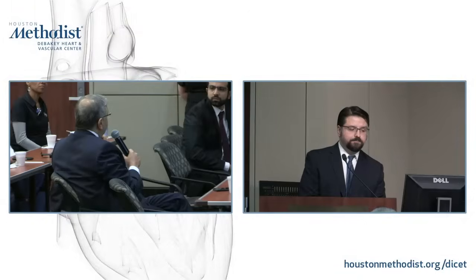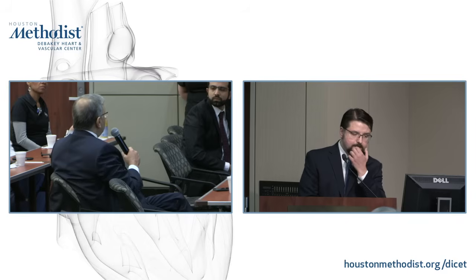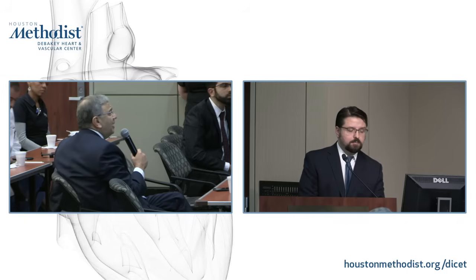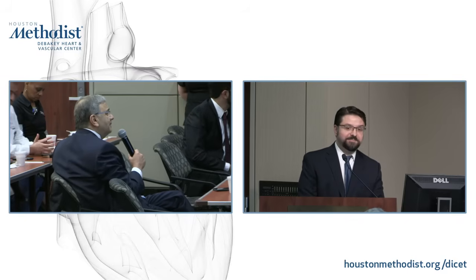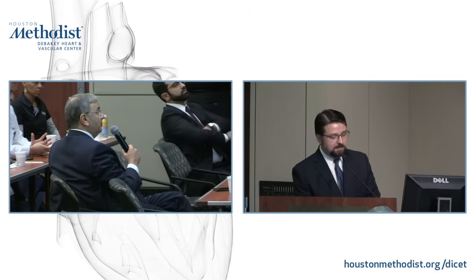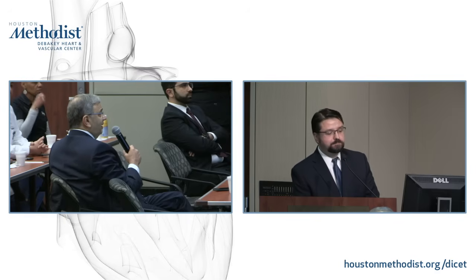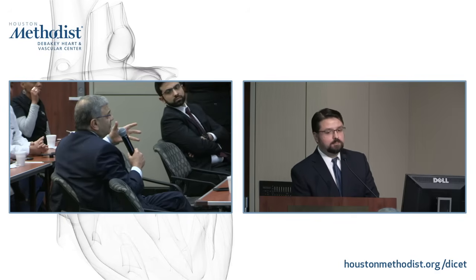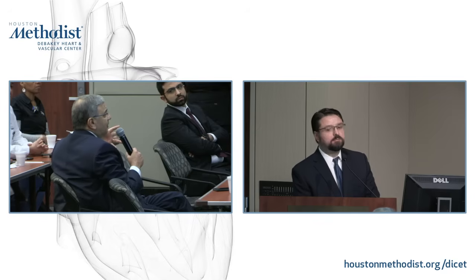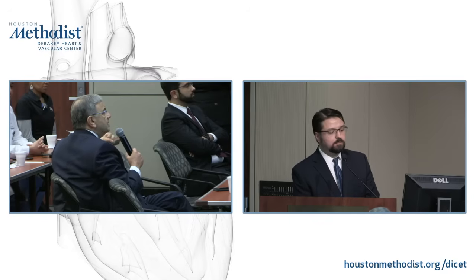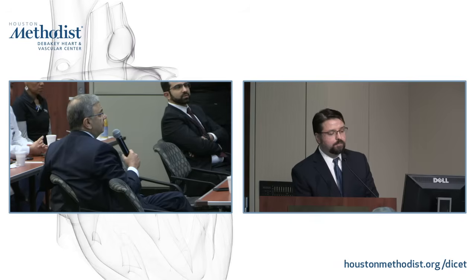What decreases the flow with that delta P? Or do you have more volume in the outflow graft? I'm just not understanding why, on a constant RPM, and the ventricle is still filling, although its pressure is maybe a little different, what decreases the flow?